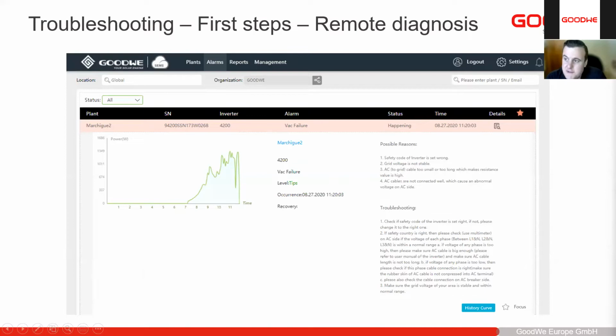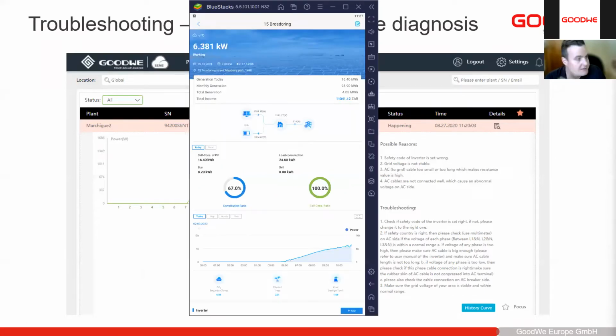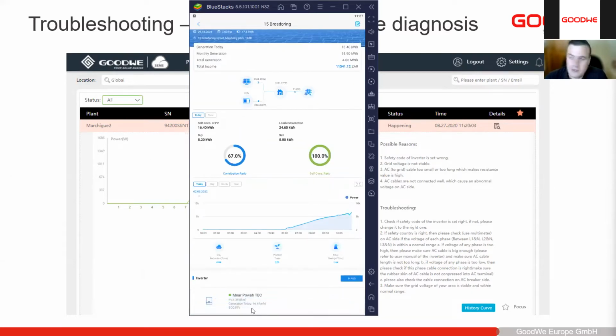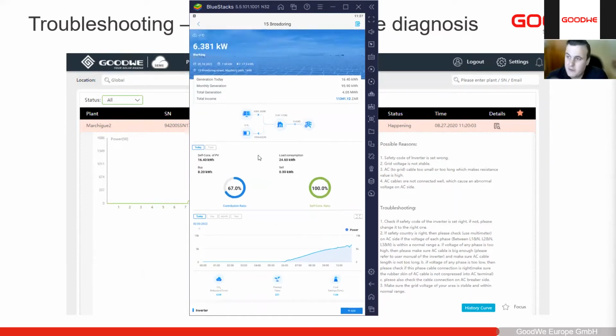One of the other places where you can have a look to see if there's any problems is on the SEMS Portal app. So very often some of the fault finding that we'll go through now is pertaining to verifying the settings on the device. So the SEMS Portal app does allow configuration of devices remotely. So especially if you have your installer account. If you don't have one and they're creating one with the GoodWe Plus, then you'll have access to this.